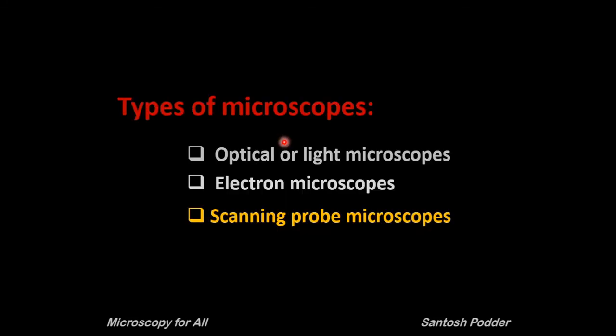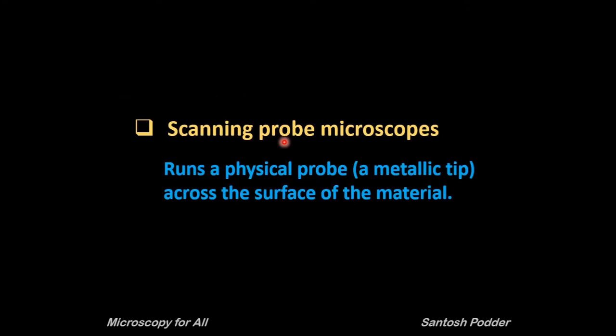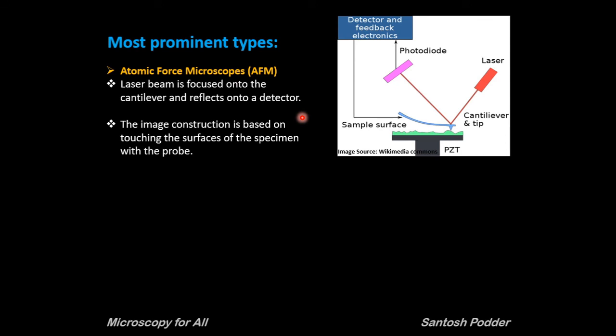Now we move to the third type: scanning probe microscopes. In scanning probe microscopes, a physical probe is run across the surface of the material — it is something like a blind person feeling their way around an object. The very sharp apex of the probe determines the higher resolution in these systems. In atomic force microscopy (AFM), a laser beam is focused onto a cantilever and reflects into a detector. The deflection of the cantilever is recorded by the computer, and an image is constructed based on the probe touching the surface of the specimen.